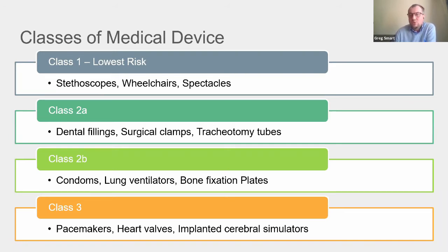You will be a medical device, a Class 1 medical device. For a Class 2 device, you have to go through that process with what's called a notified body. So they are the organizations that have been approved by the EU as auditors, in effect. And so obviously that's a harder process. There is more checking going on when an audit is conducted by a notified body.